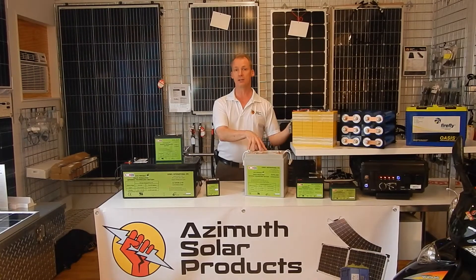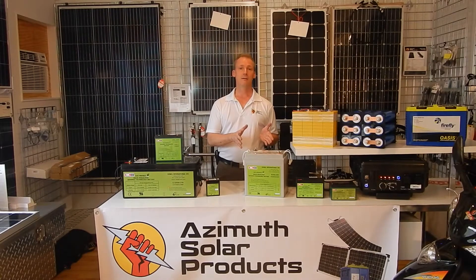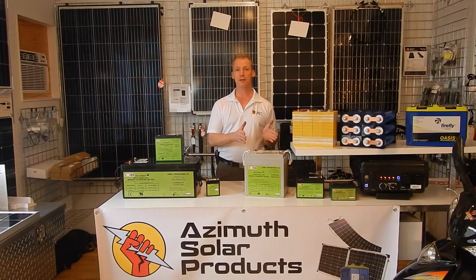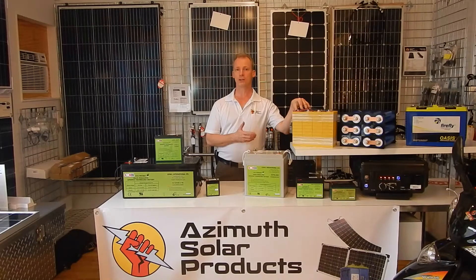As with other lead acid battery type chemistries, they weigh about 85% of what a typical lead acid battery would be for the same capacity. Versus a lithium ion battery, which generally is about one-third the weight of a lead acid battery. So if you do have weight concerns or it's a portable use, lithium ion might be better.